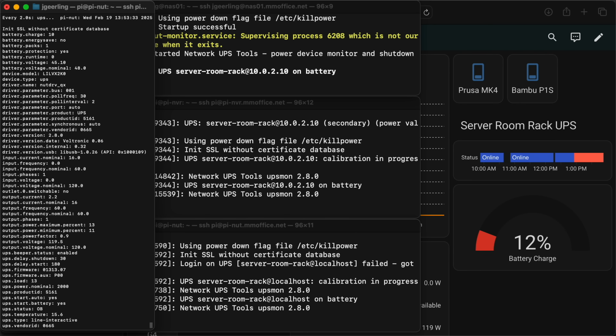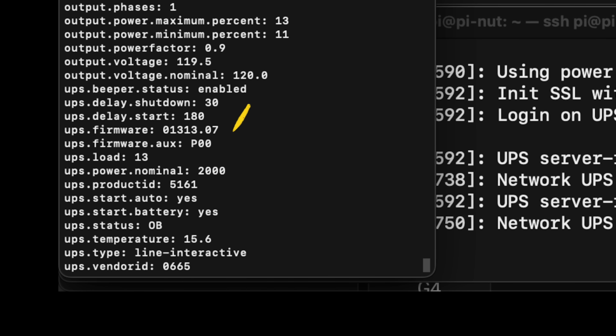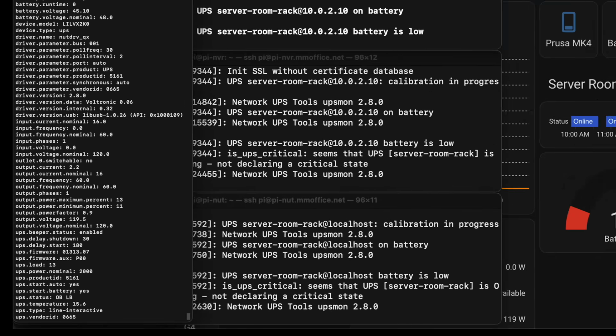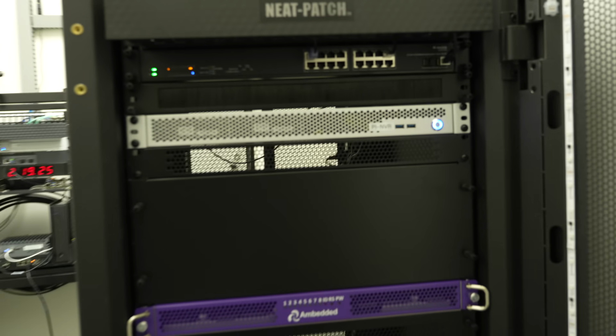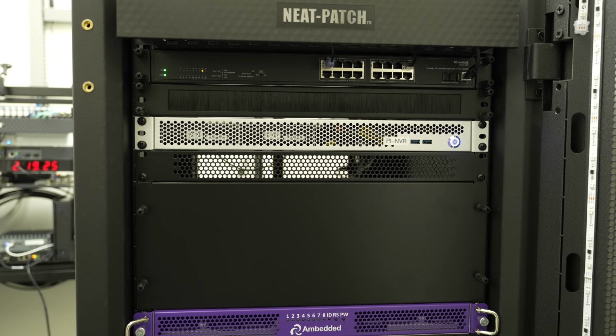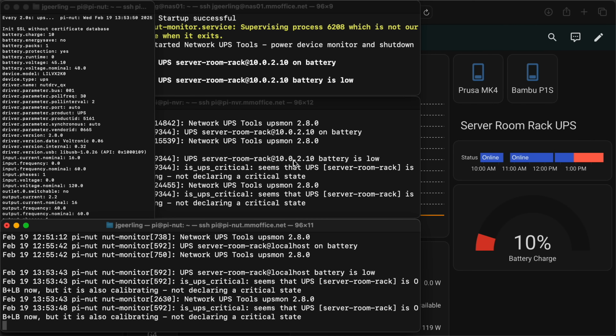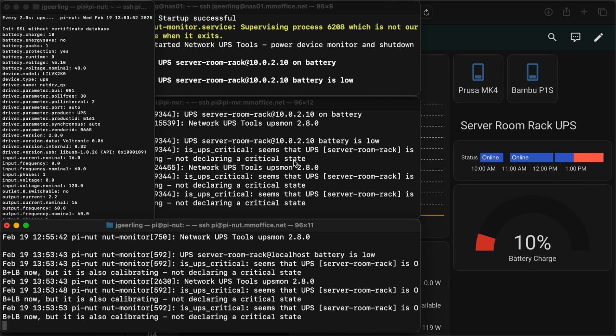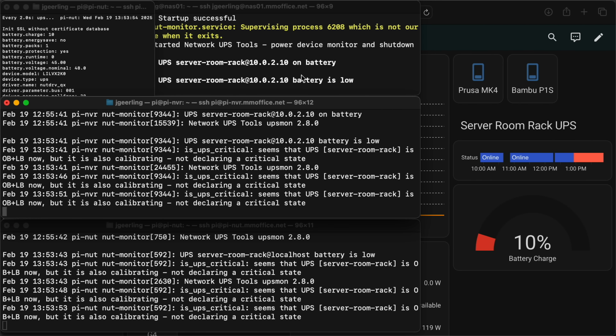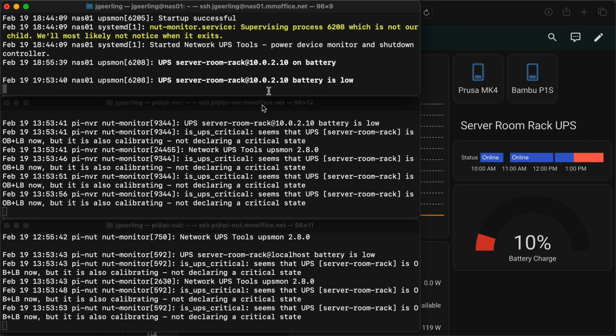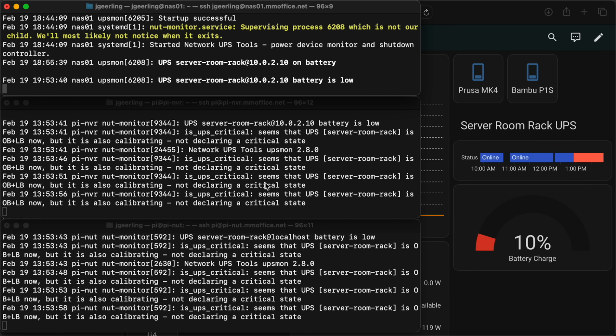So it seems like it stays at on battery, OB, until it gets down to 10 minutes, then it goes to LB. But the NVR up here did not shut down. It said battery was critical, and that it was still calibrating. I don't know what the deal is with that. I'll have to look into it, it looks like there was a bug in version 2.8.0 and 2.8.1. We'll have to figure that out.